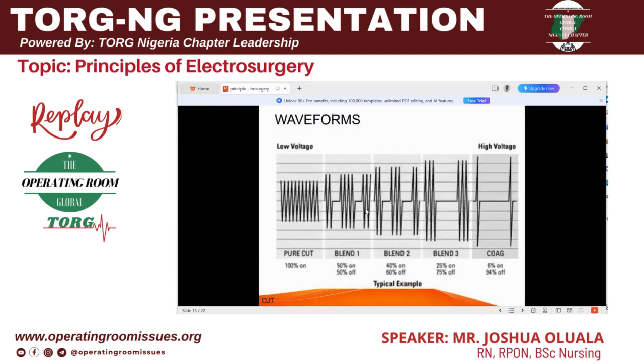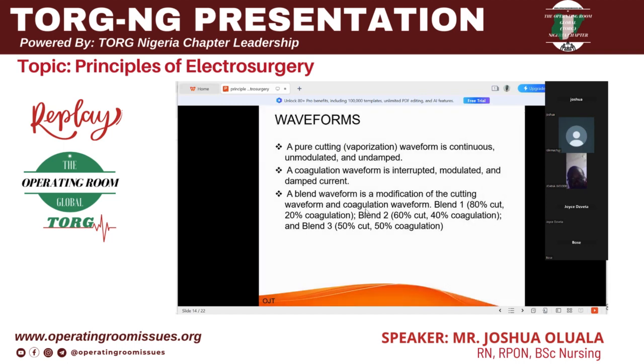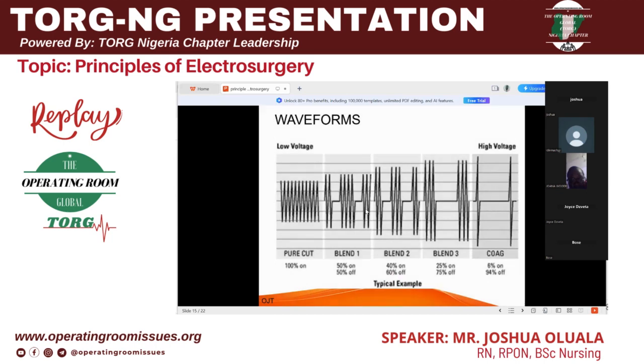And look at the waveform. Look at them in the graph. You can see the pure cut is a continuous, unmodulated, undamped waveform. You can see that. Look at blend one, blend two, blend three, and the coagulation. You see that coagulation is actually interrupted, and you can see the space on the graph. Unlike in cut, where the space is not there because it's a continuous one, this one is interrupted. And you can see the blends also, the way they go in sequence, blend one, two, and blend three.